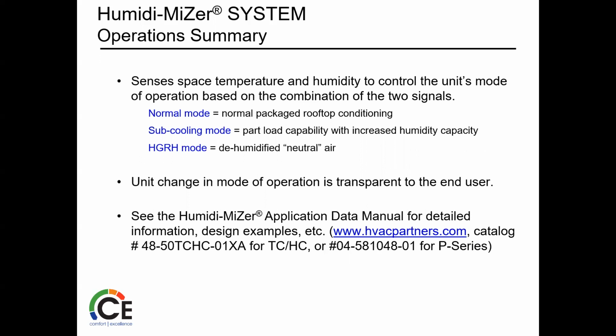So the units will stay on longer since we're supplying warm air to the room, and provide continued dehumidification of the air. So if we're just running in dehum mode, we're going to be able to dehumidify. Off-peak operation, you can have that set up depending on what you want. So there's an option there too.